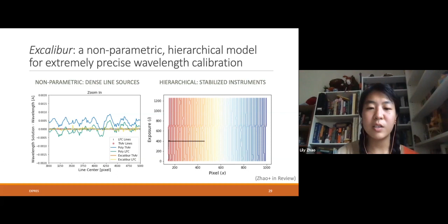Now is also the time to move to a hierarchical framework, which means using all of the calibration images you have to form a better picture of what the calibration state of your instrument is, rather than before when each LFC was fit independently to a single polynomial and didn't talk to any of the other LFC images. And so you can see the idea behind this in the following figure, which shows again the pixel position of the LFC line on the x-axis, but on the y-axis it's exposure number, which is kind of a stand-in for time. So this LFC was taken earlier than this LFC, so on and so forth.